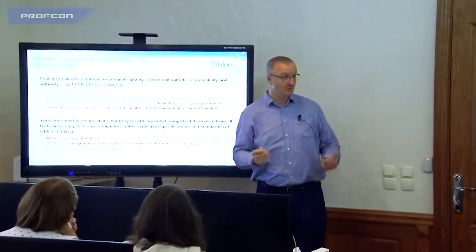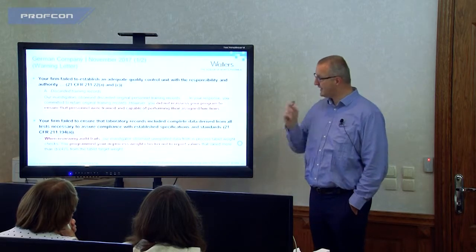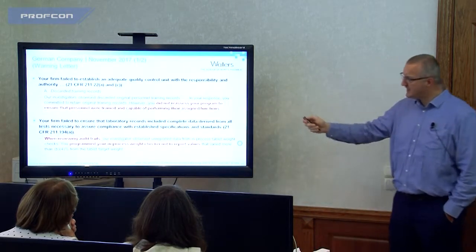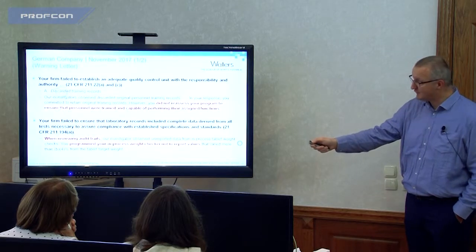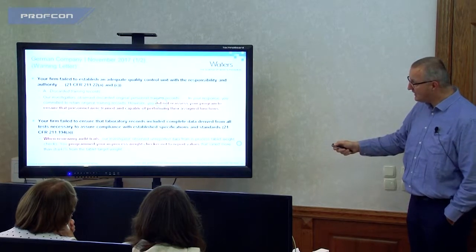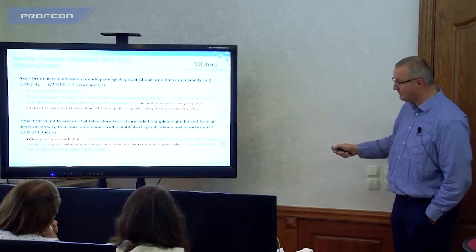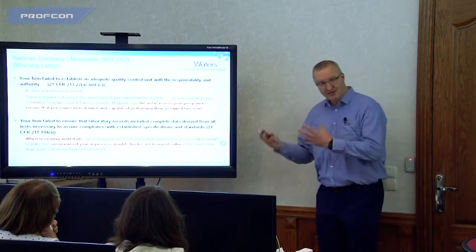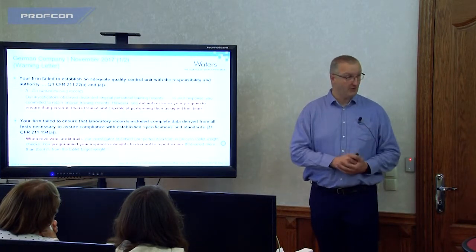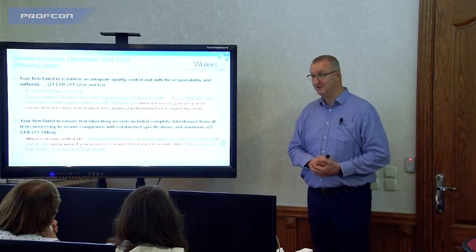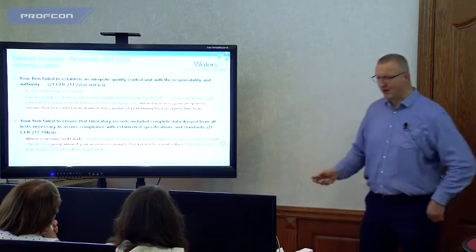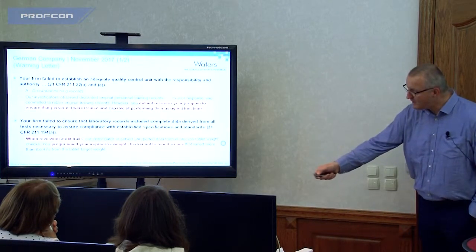Now, to give an example, a German company in 2017 got a warning letter, and the first point they raise is about people. It's about training. They say you did not reassess the program to ensure that your personnel is trained or capable of performing. So you see that they look at how people are working in the lab. Have they been trained? Do they understand the work they do? The second one that they have is reviewing audit trails.